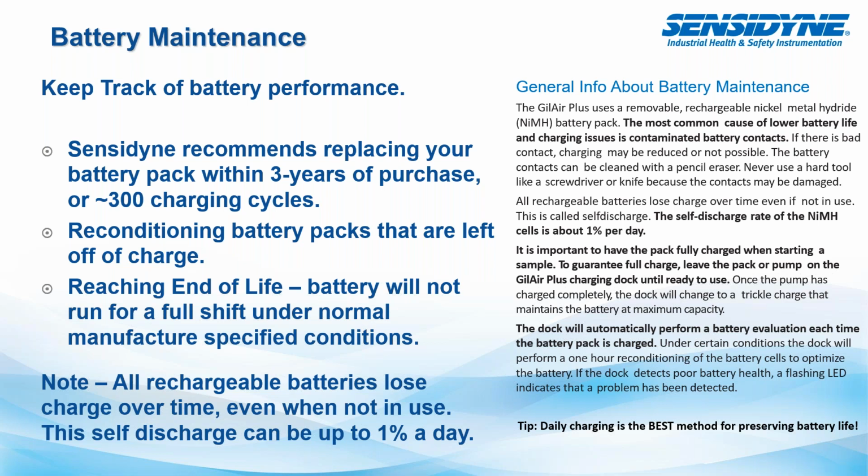Lastly, I will say that battery life can also be affected by temperature. I don't have that on the slide, but we do know that in colder temperatures, like in these winter months that we're seeing, the battery life is actually depleted a lot quicker under those colder conditions. That has to do with some of the physics involved with the battery and the energy transfer. But ultimately, under colder temperatures, if these pumps are used outside, they will have reduced battery life or reduced runtime as a result of that.